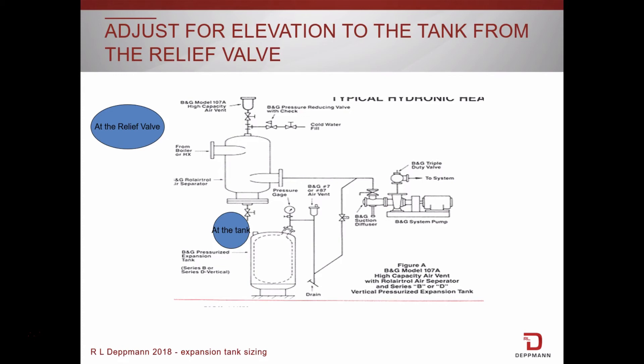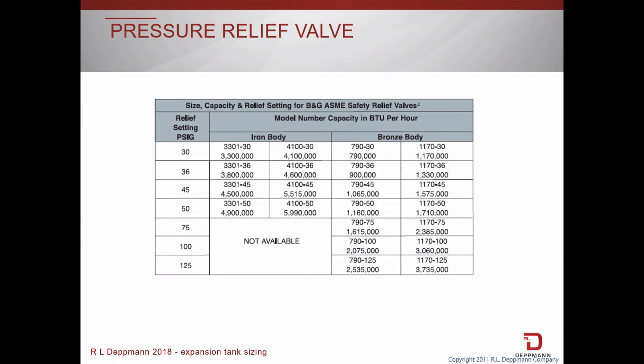So now that we know the pressure setting, how do we select the valve? This chart shows what information we need in order to select the relief valve. We need to know two items: the pressure setting, which we just calculated, and the system capacity. The valve needs to be sized to handle the BTU per hour load of the system. For example, if we determined that we wanted a 50-pound relief valve and our heating system had 4.5 million BTUs per hour worth of boilers, we would need to use the 3301-50 valve. You can see that the bronze body 790 and 1170 valves don't quite get us the capacity we need, and the iron body 4100 is much more than we need.